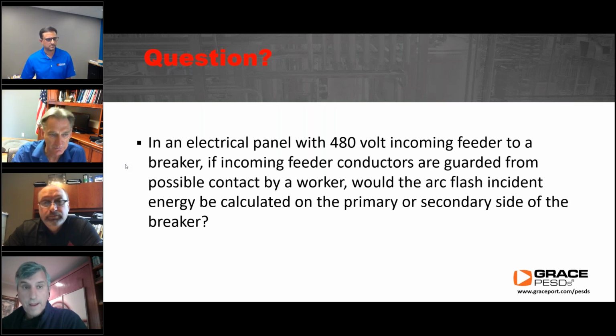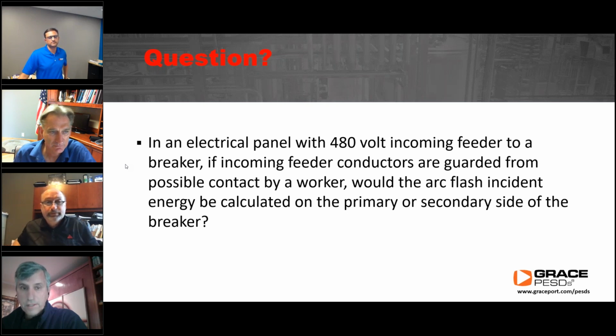We call it ignoring the main. We assume that if a fault happens anywhere in that panel, there's going to be enough ozone produced to make a conductive cloud, which may involve the source breaker. You'd label that to protect your people, but you'd also have tons of incident energy in many cases, so you wouldn't be able to do as much work. There's really not a right or wrong answer. It's an engineering call as to whether you include the main when you do those calculations. The other part of the discussion is about guarding and whether you have what we call effective isolation.